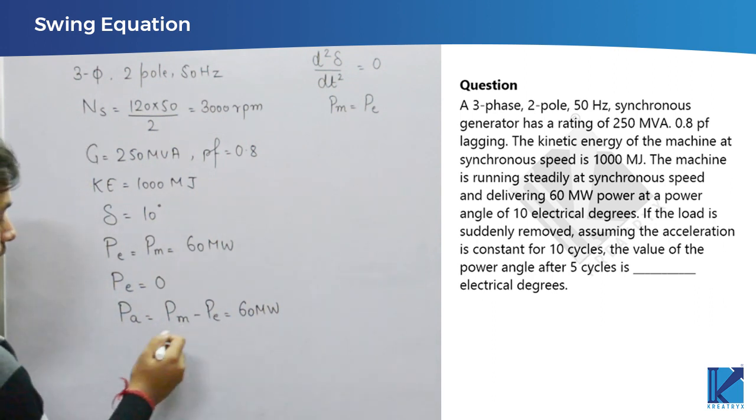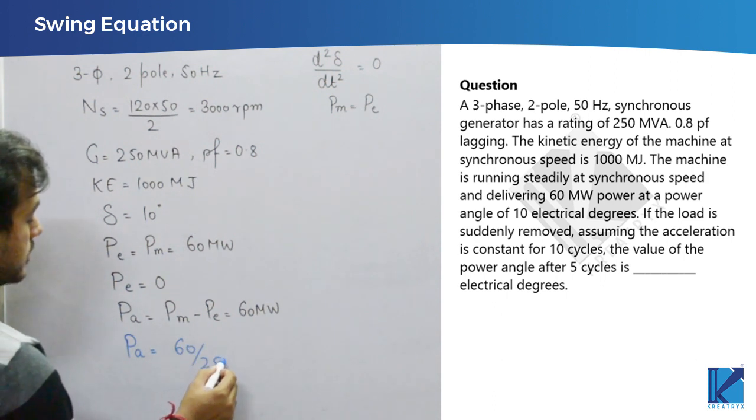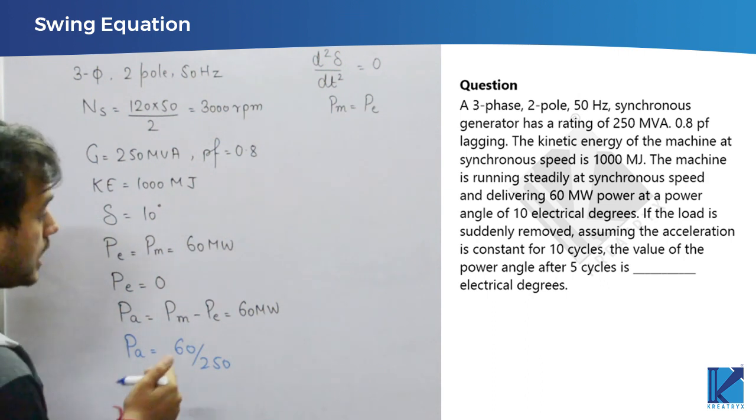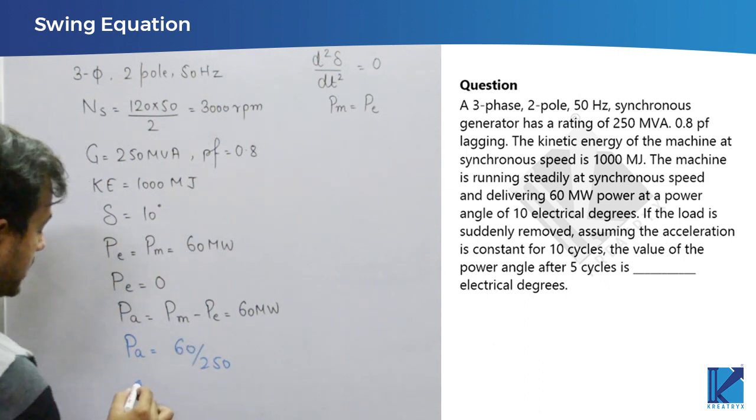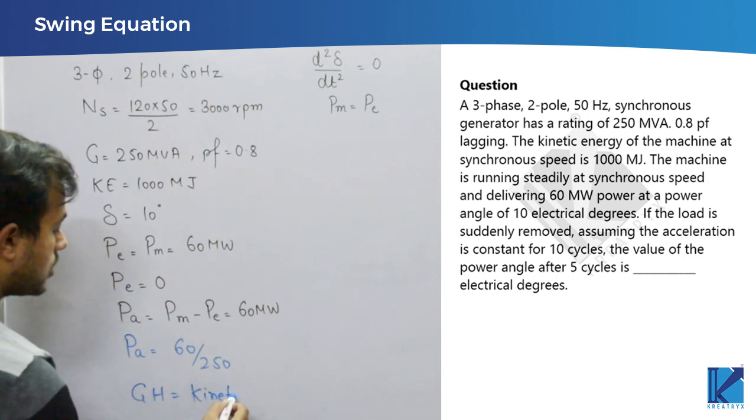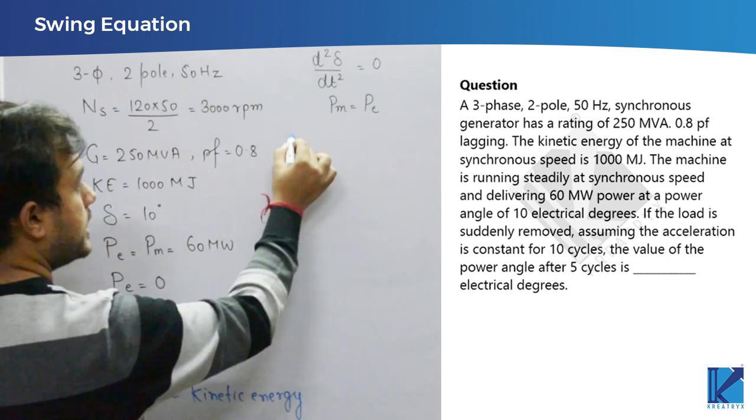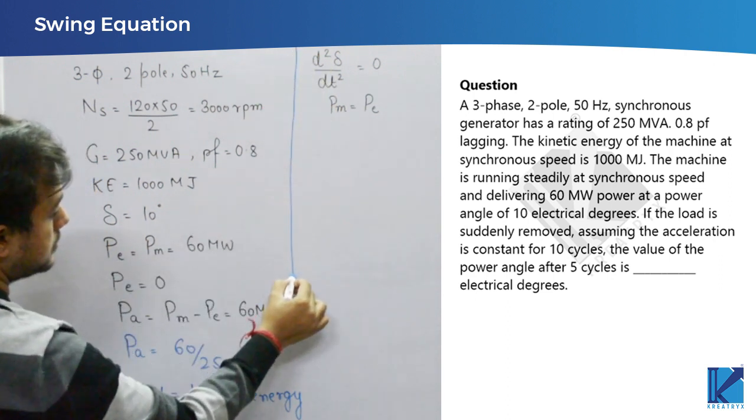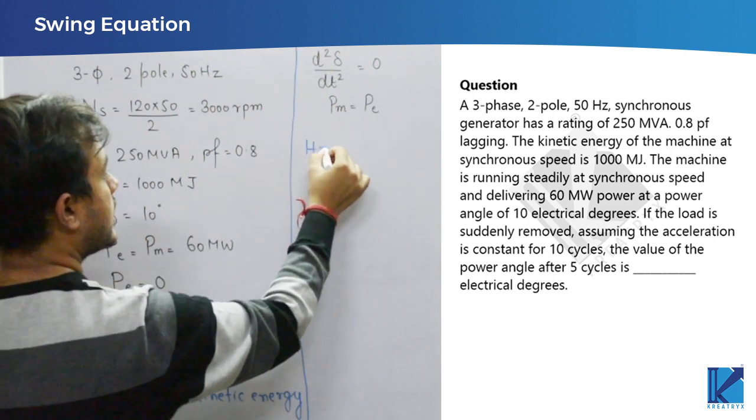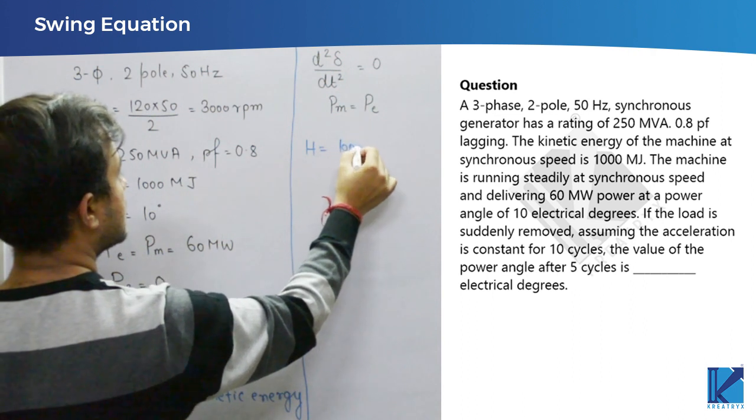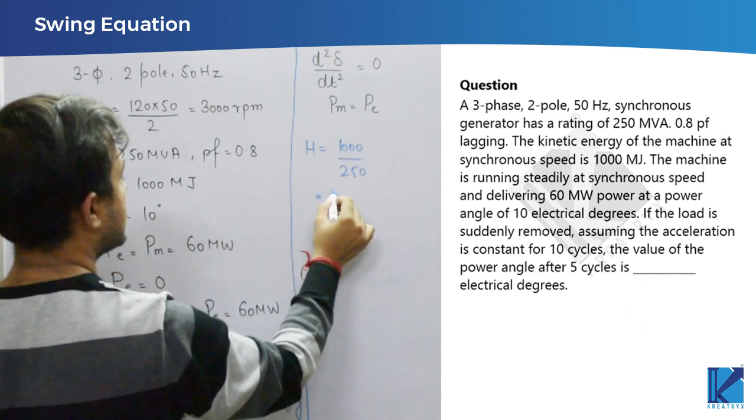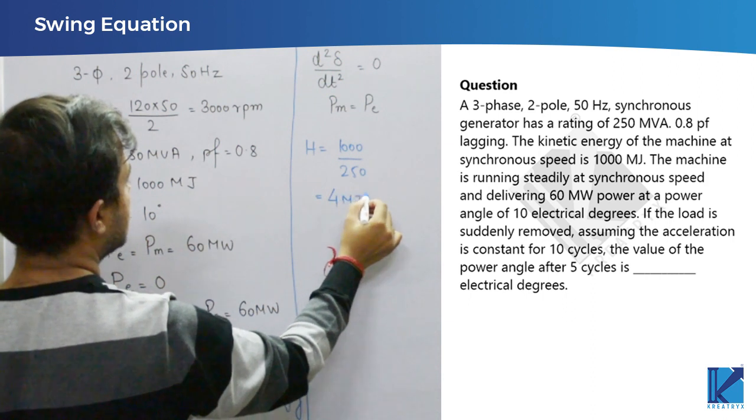So, first of all, let me bring this into per unit. It will be 60 by 250. That is, power upon base. That is in per unit. Now, if you want to find out H, then you have to remember GH is basically equal to kinetic energy of the machine. It means that H equal to 1000 by 250 which means 4 megajoule per MVA.